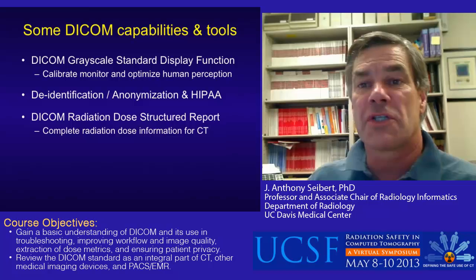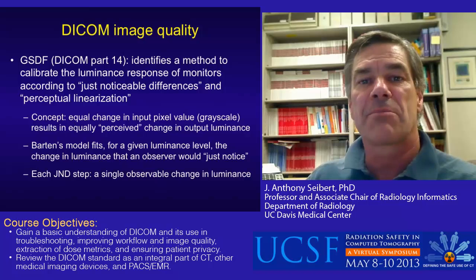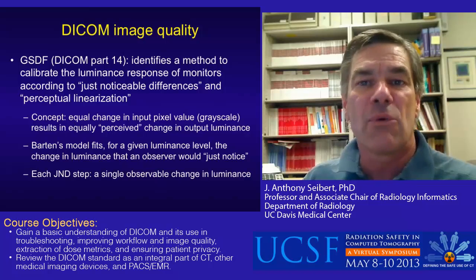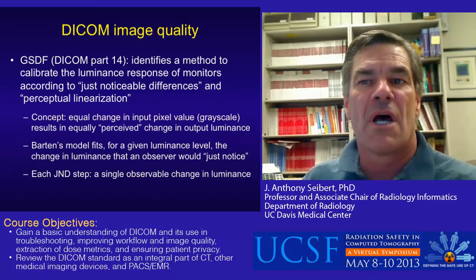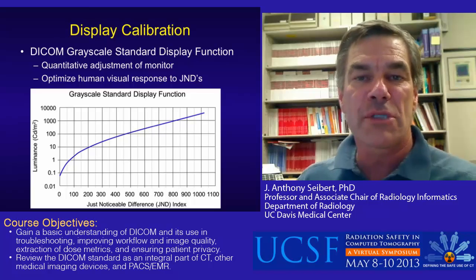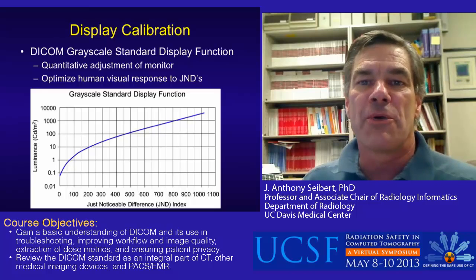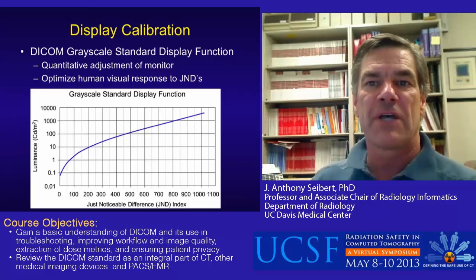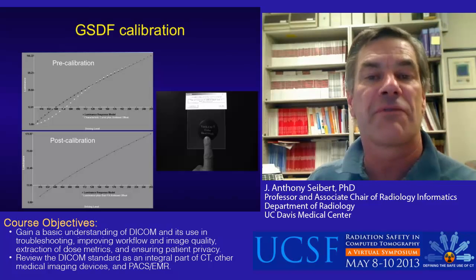The Grayscale Standard Display Function, GSDF, also known as DICOM Part 14, identifies a method for calibration of monitors using the concept of just noticeable differences and perceptual linearization. The model is based upon an equal change in input digital pixel value that results in an equally perceived change in output luminance. A researcher named Barten described this model. The Barten curve represents the just noticeable differences as a function of display brightness of a grayscale liquid crystal display monitor. By measuring the response of the monitor to variations in digital pixel driving level, a translation table can be used to map pixel values from the image to overcome the non-ideal characteristics of the monitor response.